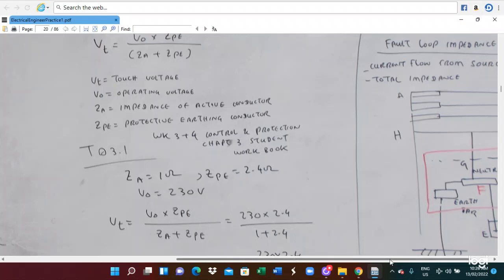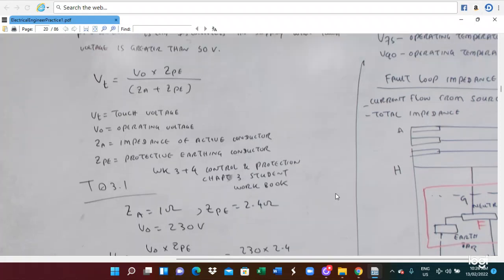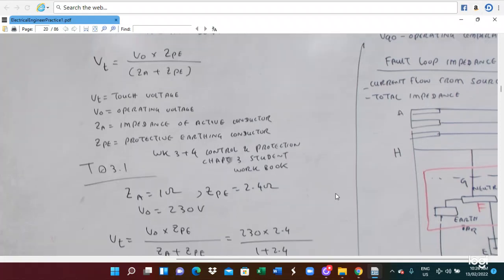So as an electrical engineer, before you disconnect anything, especially when you are upgrading the electrical system, you have to disconnect all the electrical supply and all the wires, and you have to reinstall the whole system. So before you disconnect anything, you have to be aware of the touch voltage. This is the touch voltage calculation.